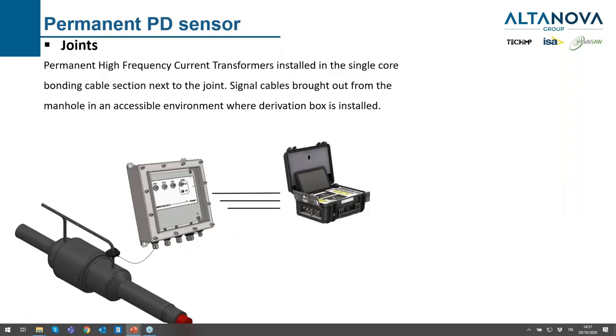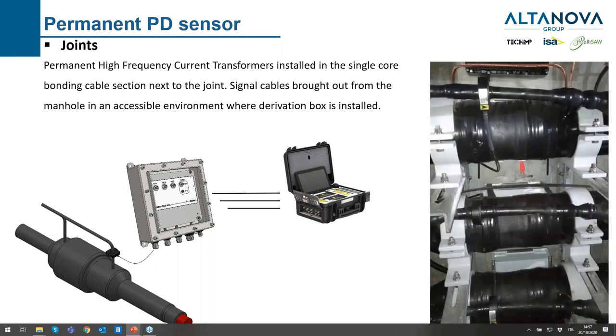In the joints, we can also install HFCTs. They should be installed on the single-core side of the bonding cable, next to the joint, and the signal can be brought outside with a dedicated box. This is one of our customers — you can see the HFCT installed in the single-conductor bonding cable.